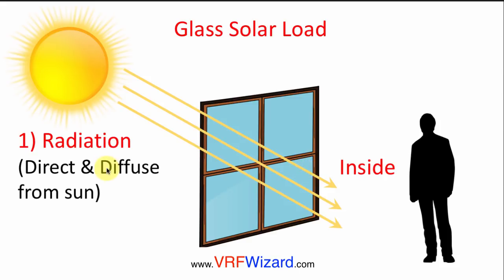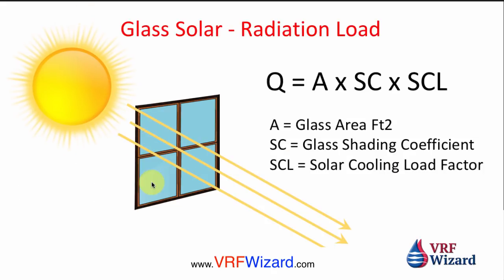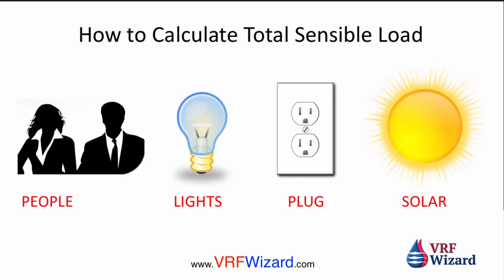The other way heat enters is radiation — direct and diffuse from the sun. The equation is: Q (BTUs) = Area (square feet of glass) × Glass Shading Coefficient × Solar Cooling Load Factor. ASHRAE provides shading coefficients, which are affected by window blinds and venetian blinds. The Solar Cooling Load Factor depends on orientation (south, east, west, north), geographical location, time of day, and month of the year.